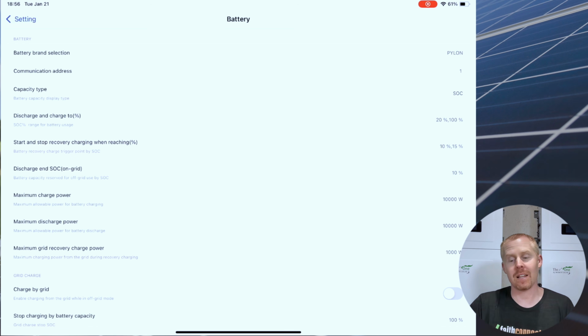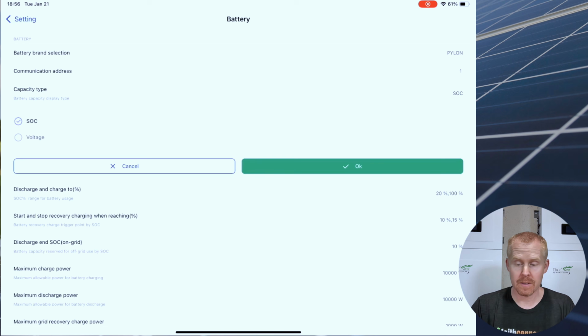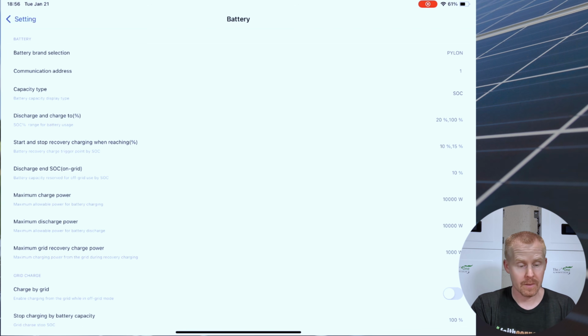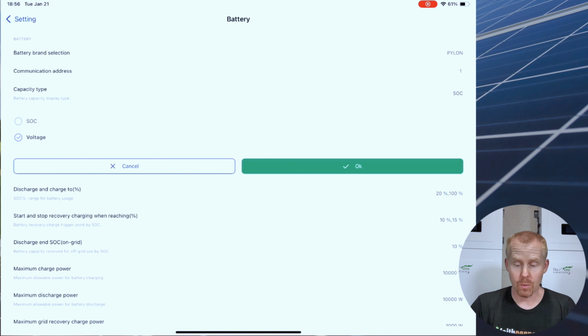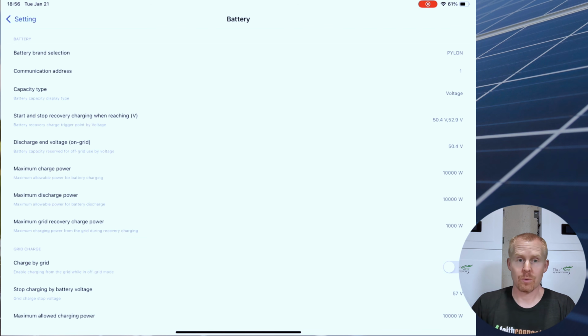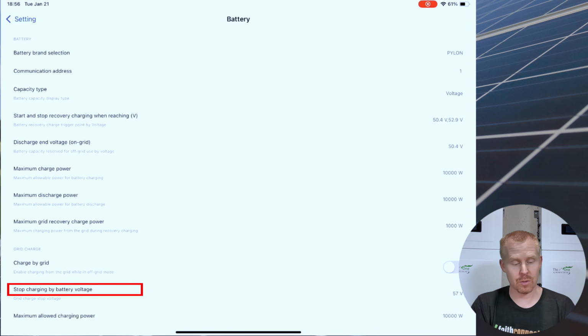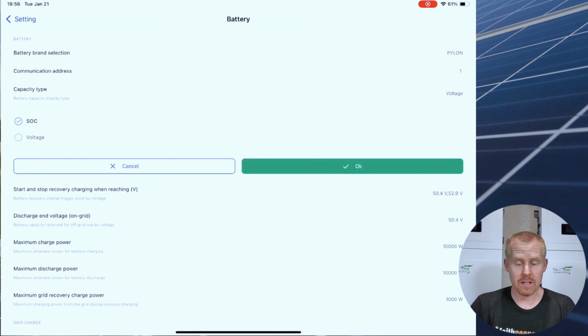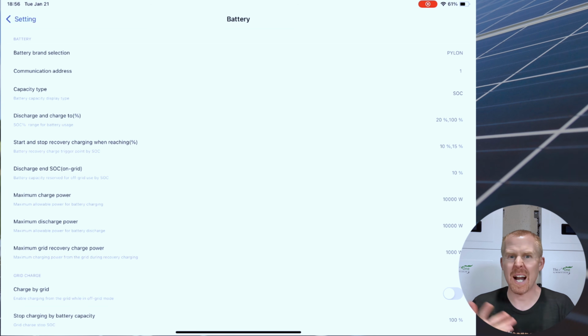You can see I've got the pylon protocol selected right now. So it wants to know what's the battery address. Do you want to control your different settings based on the state of charge of the battery, or do you want to use the voltage? And if you switch to voltage, it will change all fields related to state of charge and show voltage instead. So you can see start, stop voltage, discharge voltage. Down at the bottom of the screen, stop charging battery voltage. But I want this to be state of charge. It's just a little more accurate.